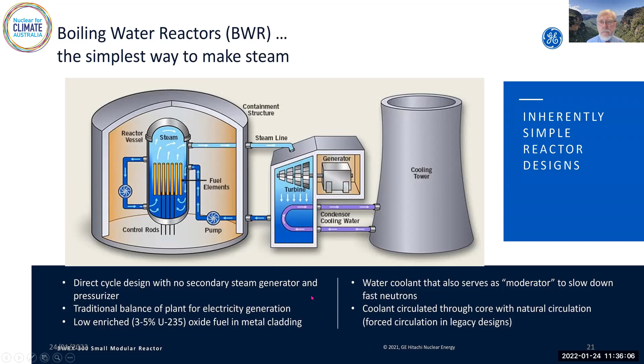It uses low enriched uranium, 3 to 5% U235. The water coolant also acts as the moderator. I won't go into the nuclear physics of that right now, but it serves two purposes: not only cooling and heat generation, but also moderation. And in the case of the reactor we're talking about, this pump isn't required - it uses natural circulation on the primary circuit.